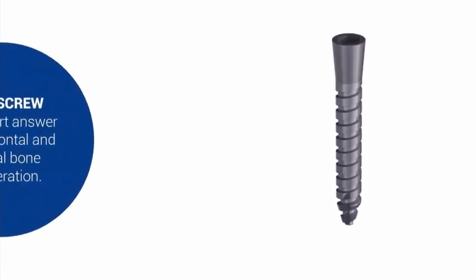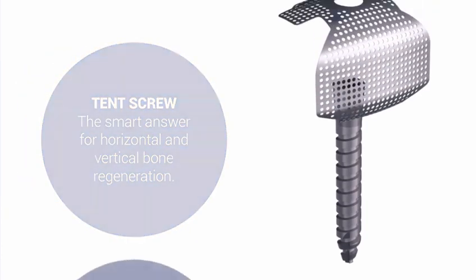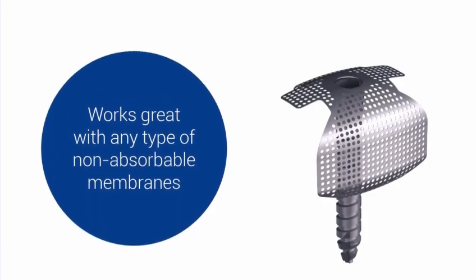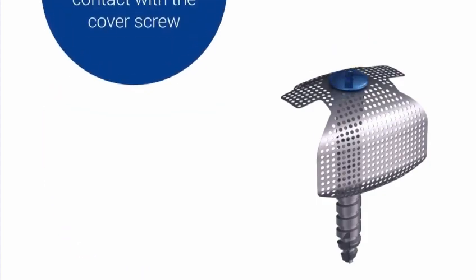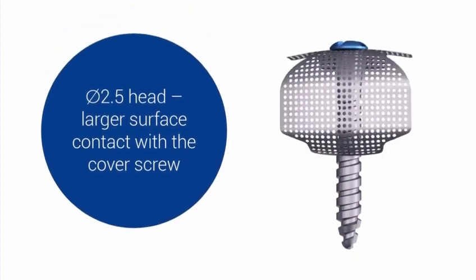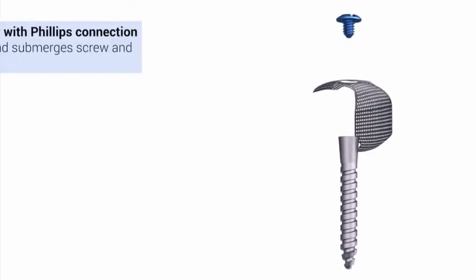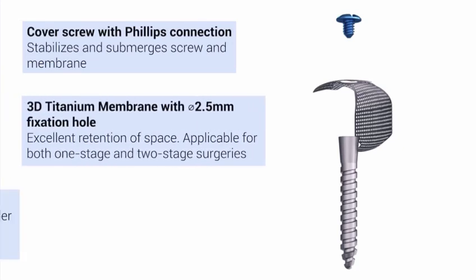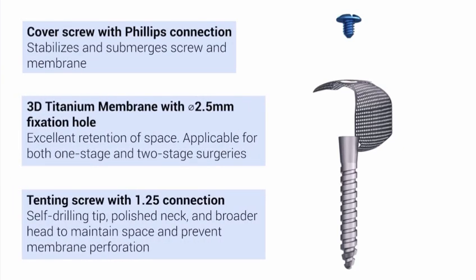The DSI-2 Component Tenting Screw provides a reliable solution for membrane fixation of any type. Even first-time users can expect predictable bone regeneration using it with titanium mesh. Its 2.5mm diameter head provides a broad surface area to help prevent membrane perforation or tearing, and its aggressive tip and thread design engages bone for precise placement without pre-drilling, even in cortical bone.